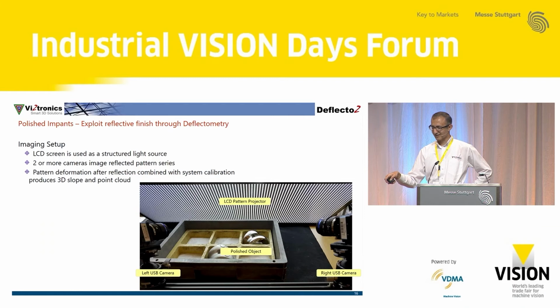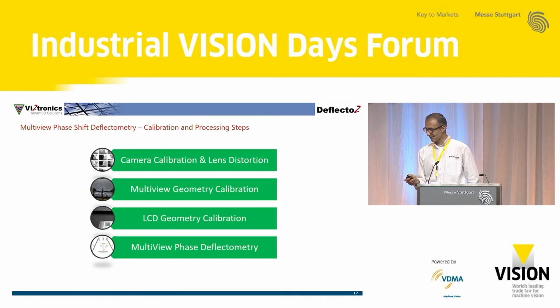in the reflected object, right? One reason we have to use phase shift or some kind of defocus-resistant analysis mechanism is that the camera is focused on the object, but the pattern is further away. So you can focus on the object, but not on the pattern. The pattern would always be out of focus, and that means any kind of defocus-resistant structured light approach is the only one which is going to work. If you're using binary or some kind of focus-dependent structured light, that won't really give you the result and resolution that you require.